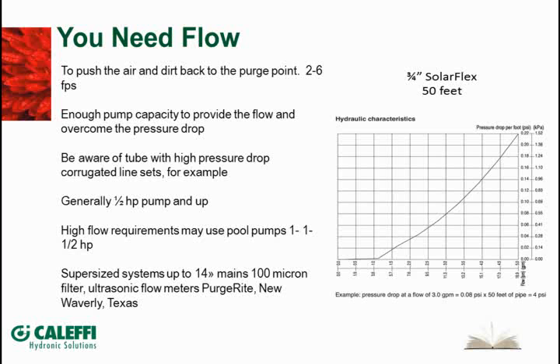And they can also filter it. One of the companies that I met at the IGSPA show a couple years ago was out of Texas, and that's all they do: they go around and purge big commercial systems and big geo loop systems, and they can purge up to a 14-inch diameter main. They'll put a 100-micron filter on it so they can get the fluid filtered as they circulate it through the system.